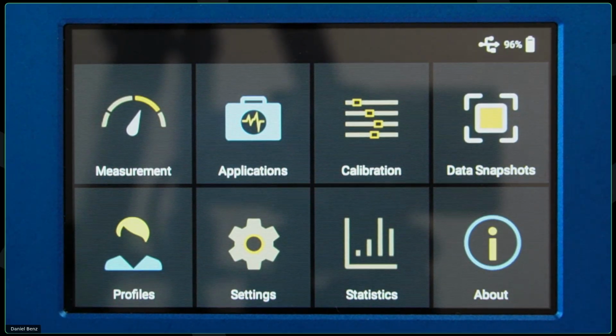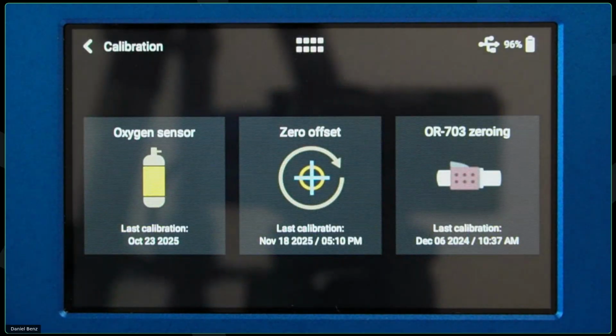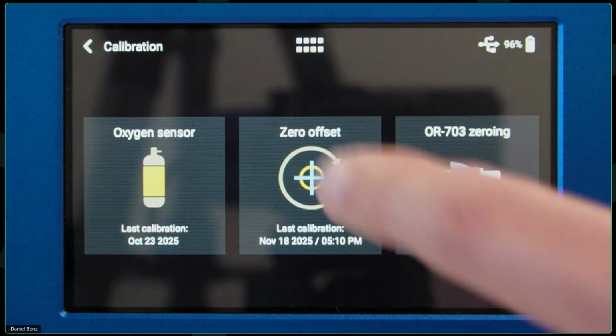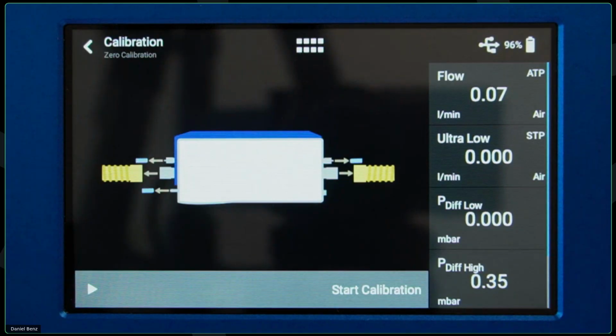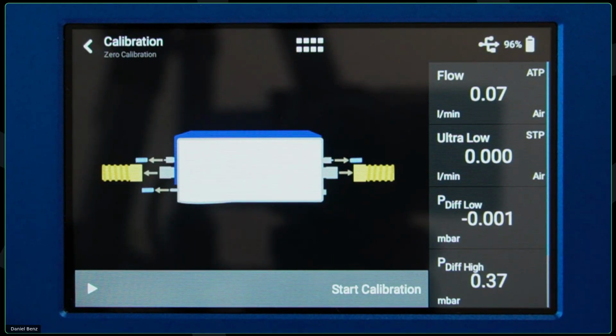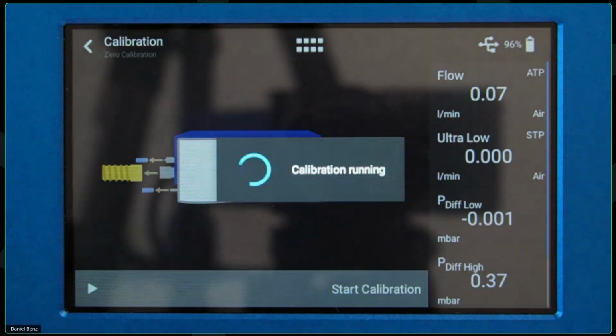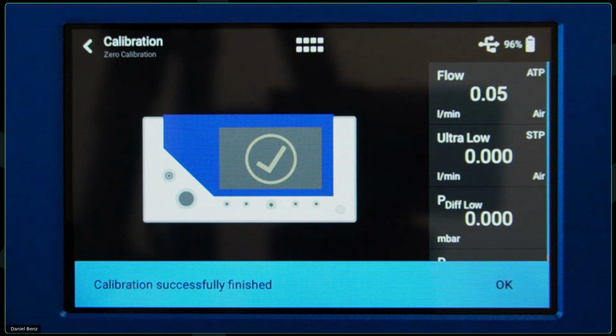Before we hook up a ventilator to the FlowAnalyser, let's prepare the device as we would do it in a real life scenario. Some of you that are familiar with using gas flow analyzers probably know that usually what we typically do before we start measuring is to perform a zero offset calibration. To do that, probably you can guess it's in the tile calibrations. If I enter that one, I see in the middle here the possibility to start my zero pressure calibration. The device asks me to disconnect all the tubings, and then I can just start that from there. And as you can see, it's now running, and after a little while it was successful. So we can confirm here and leave this screen.